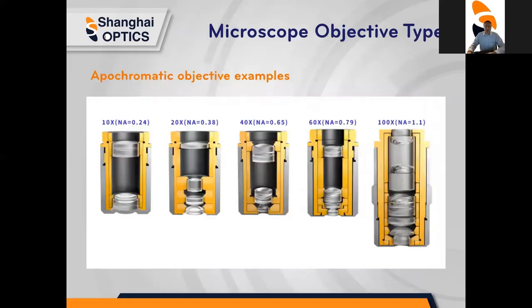Here are some examples of apochromatic lenses, which are corrected for three colors. In the images you see the magnification and numerical aperture for each objective. These objectives are complicated and consist of many lens elements in the lens barrel. The higher the NA, the greater the amount of elements used, and the higher the resolution.